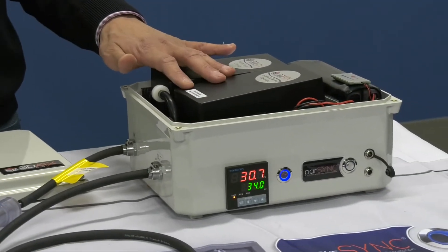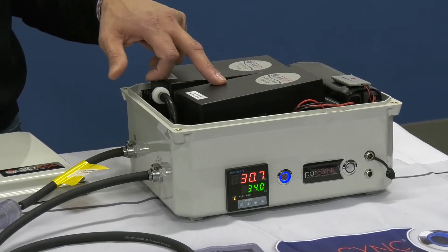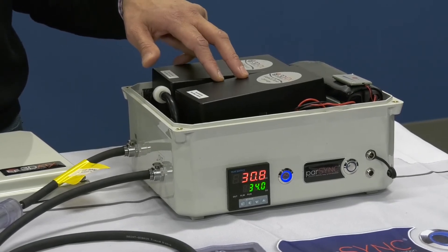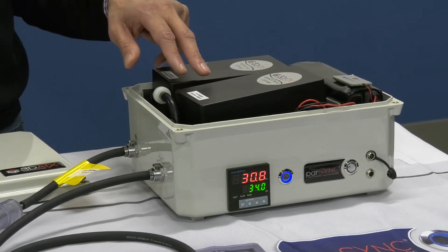The gas cartridge has three sensors: an NDIR that measures CO and CO2, an NO electrochemical sensor, and an NO2 electrochemical sensor — so we measure NO and NO2 separately.